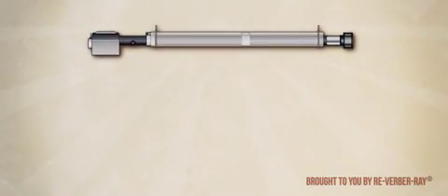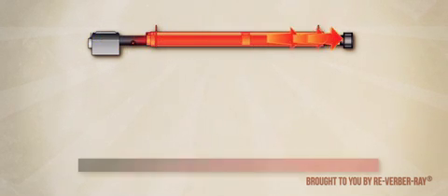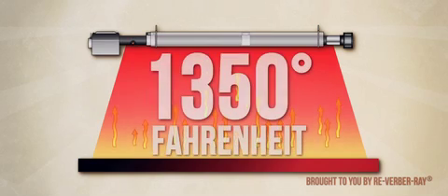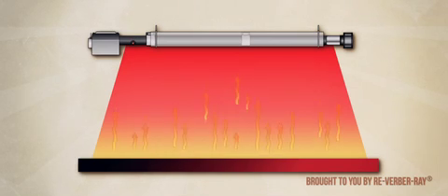In a low intensity heating system, a flame is ignited within an exchanger, producing hot exhaust gases which travel through the tubing, reaching temperatures of up to 1350 degrees Fahrenheit emitting infrared energy. Low intensity heaters are commonly direct vented.